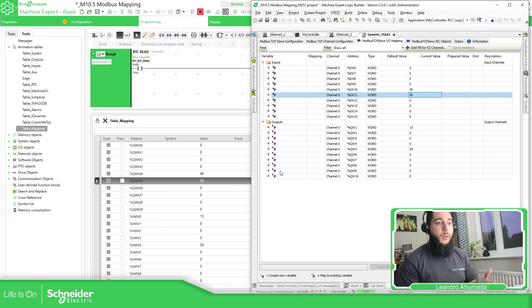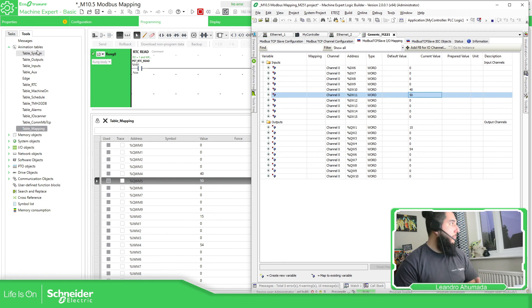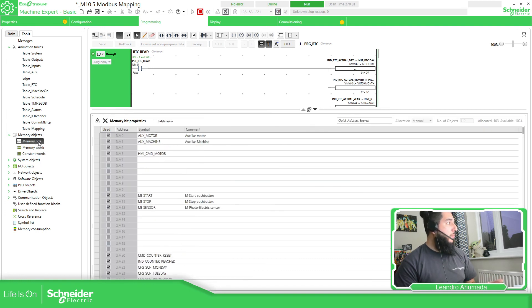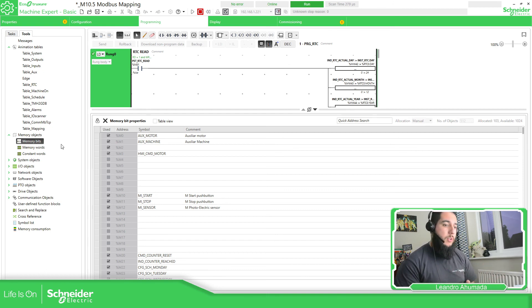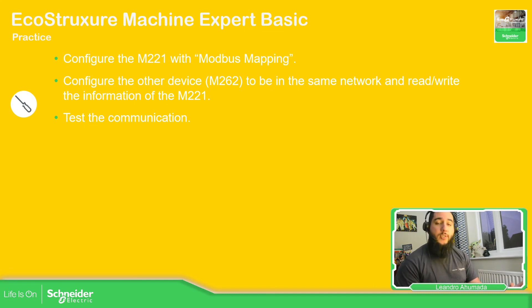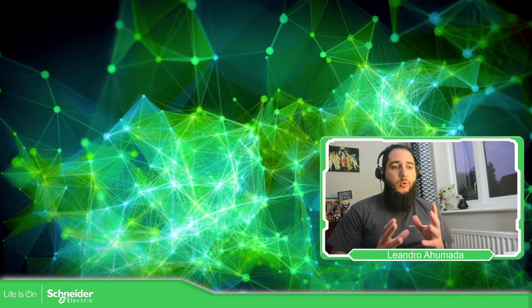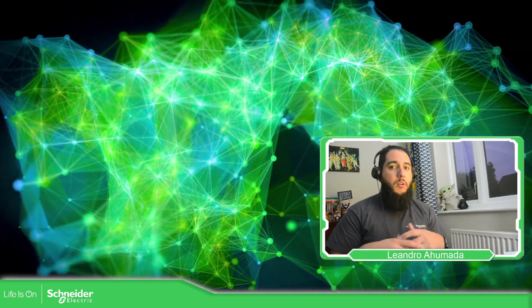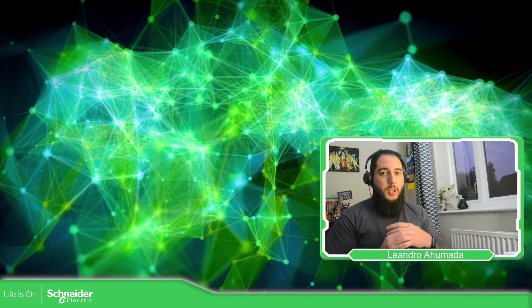One alternative solution would be to read and write directly to the %MW registers without using the unit ID, accessing the memory word variables on the M221 directly. For that approach you would likely need to use read and write function blocks on the M262. But Modbus mapping is just one easy way to have all the data together for reading and writing. Now it's your turn to test this out — you can use the M221 or another PLC. This is how you use Modbus mapping on the M221 to easily share information with another device like the M262, M241, or any other PLC. Thank you very much for watching and I'll see you on the next one.